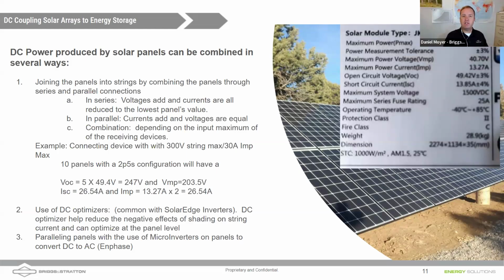We're just going to not even touch that. We're going to take the AC out of that SolarEdge and send it right into the hybrid inverter, like an EG4. I guess where I'm going with this is that it might be tempting to go up to the roof and rip out that string inverter and make it a DC coupled system. That might be possible. We might be able to take that DC that was otherwise going to a string inverter and now just feed it right into the charge controllers on the EG4.